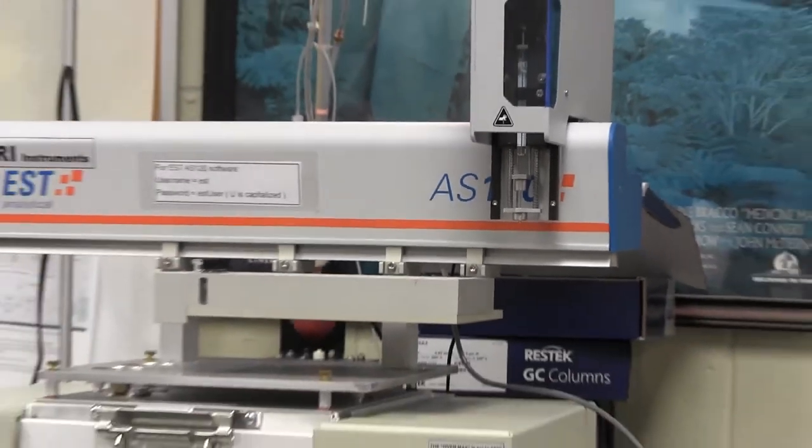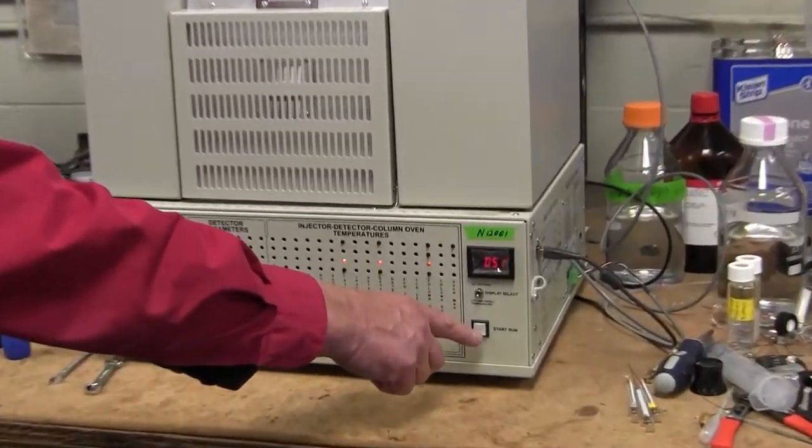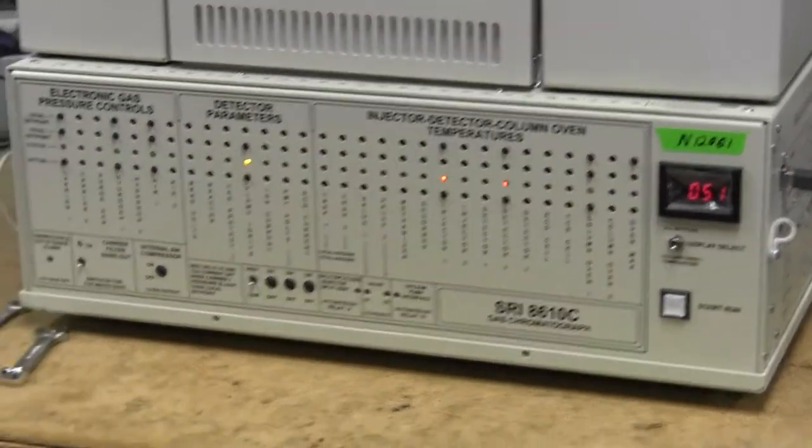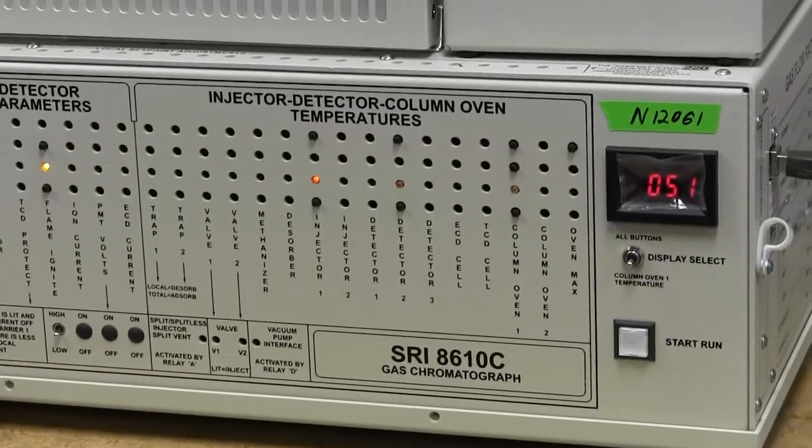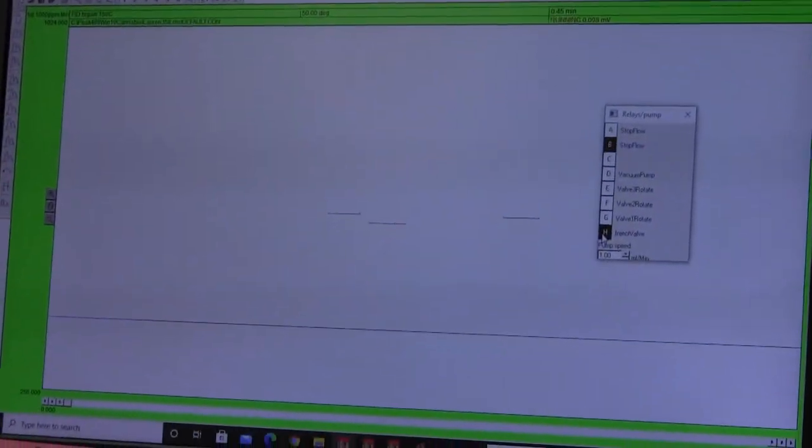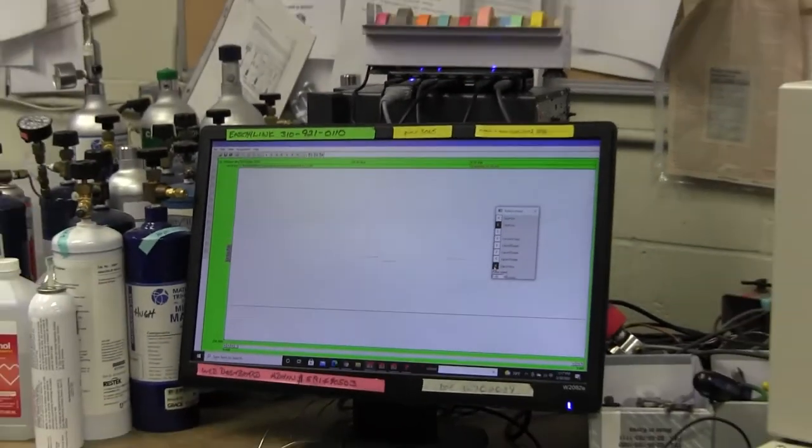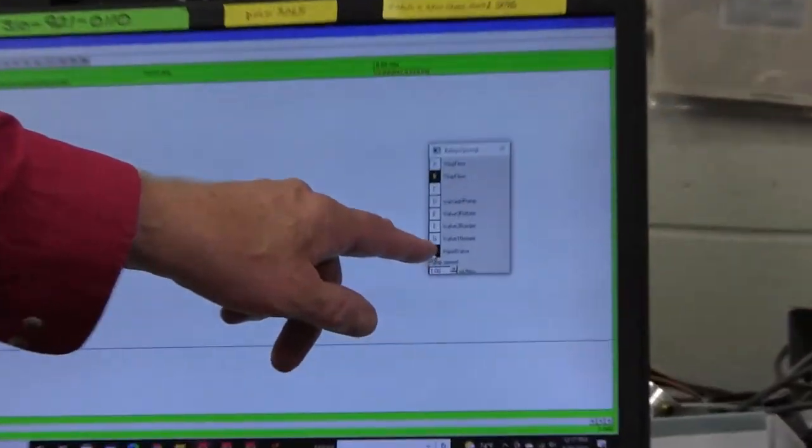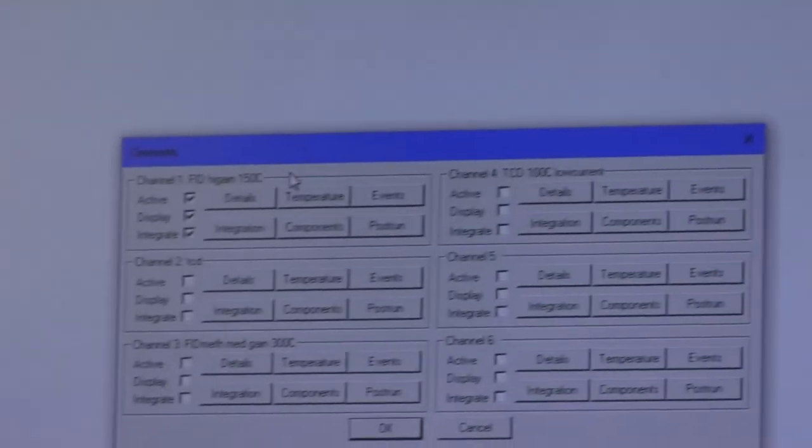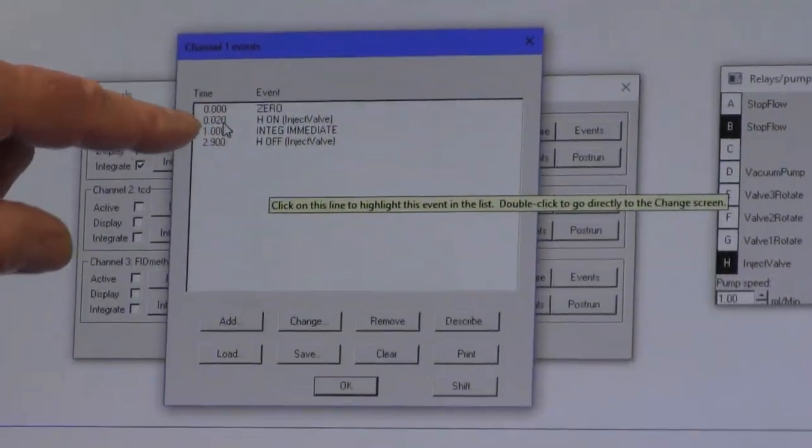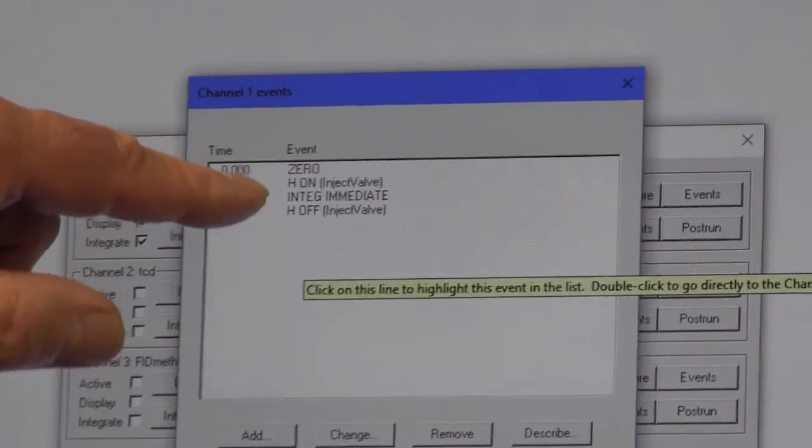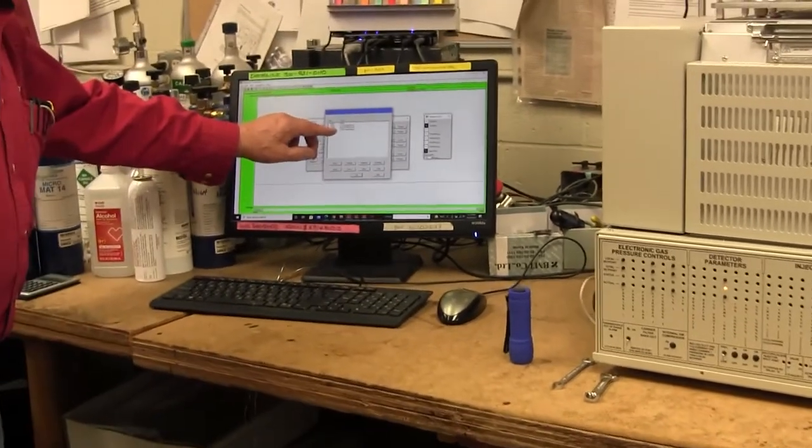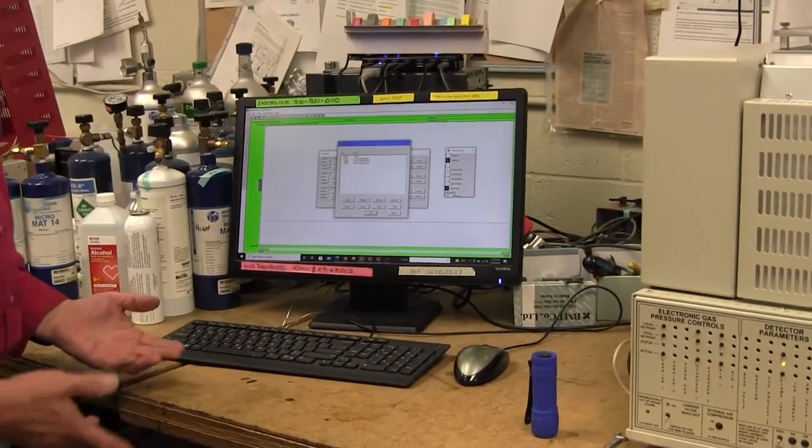So it's doing what I told it. Right now notice that the start button here, now the light has gone out. That's because we inhibited it from turning on again by clicking this relay H on the software. So that's important because if the light were to come on again, the auto sampler would go and inject again and we don't want that until the analysis is complete. So what we do is we turn this relay H on via the software. We go to edit channels and then events for channel one and we put an event in very close to the beginning of the analysis. In this case, it's 0.02 minutes we turned relay H on and what relay H does is prevent this light from coming on and relay H turns off at the end of the analysis. So at the end of the analysis now, the thing that's preventing the next cycle from beginning is when this light turns on, the next cycle will start.